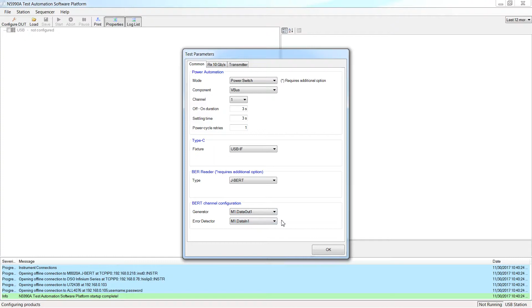We go now to the receiver 10 gigabit per second tab to configure the loopback training and the error detector. Several link training methods are supported, depending on the DUT type and the hardware. For this tutorial, we are using a device, so we will select warm reset. If the DUT was a host, we would select power on reset. If we were a silicon vendor and want to test our PHY without a USB LTSSM, we can test it without a proper link training by selecting vendor specific. We can select how the electrical idle for LFPS signals is generated out of several options: a static zero signal, a half-rate clock signal, and the M8020A idle or squelch feature.